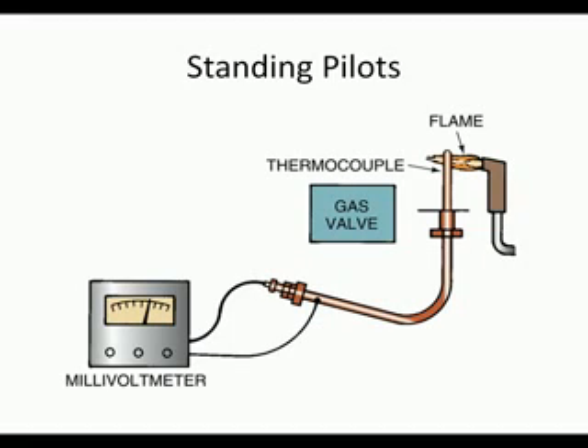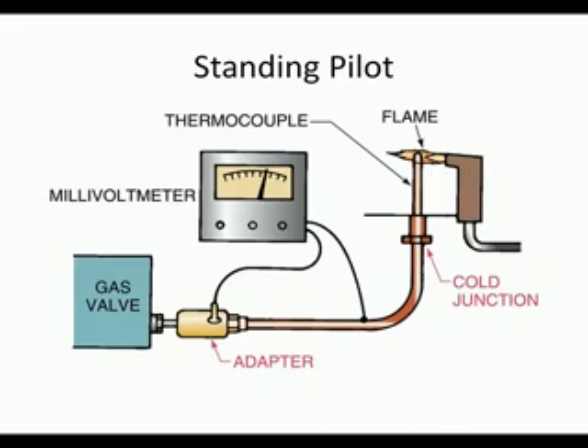Common problems with standing pilots: the pilot will not stay lit. If it's a problem with the thermocouple or main gas valve, pilot not lighting is a problem with the gas supply unit, or a pilot burner being clogged, or the pilot line being kinked or restricted. Standing pilot systems can be tested. Use a millivoltmeter on the end of your thermocouple lead. You should read 25 to 30 millivolts when flame is applied.